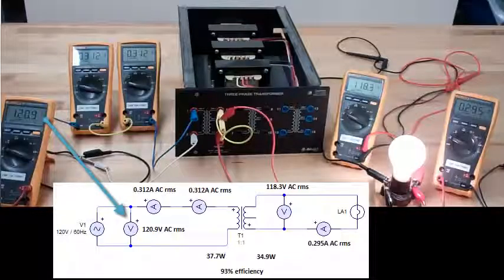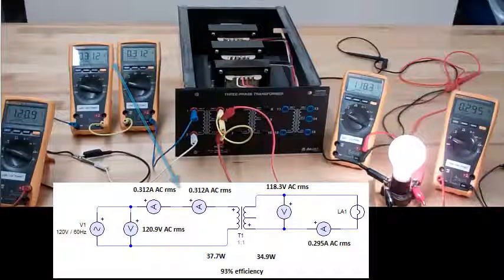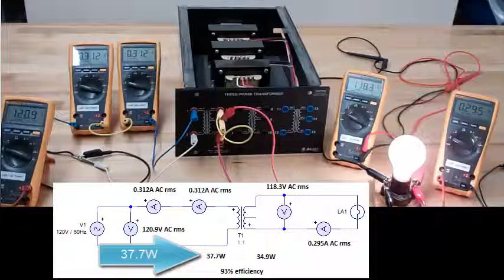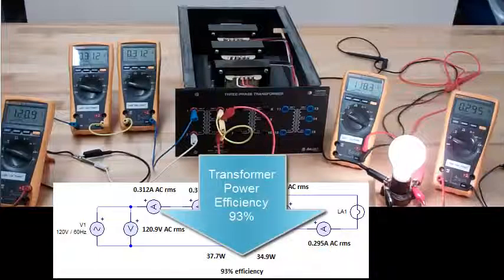Input voltage is 120.9 volts. Input current is 0.312 amps. Output voltage is 118.3 volts. Output current is 0.295 amps. That's a 37.7 watt input power and a 34.9 watt output power for a transformer power efficiency of 93%.